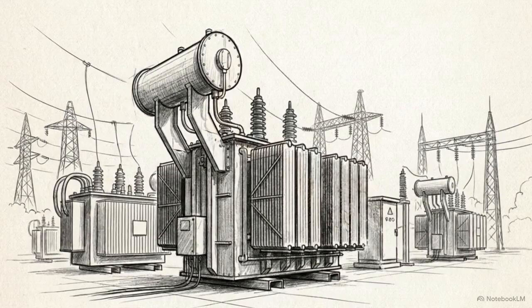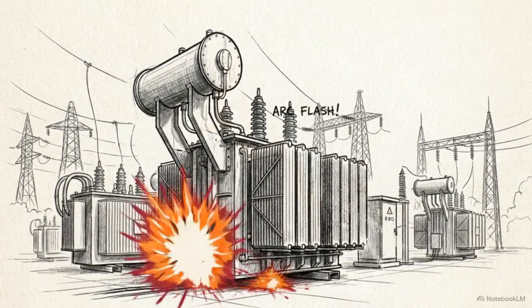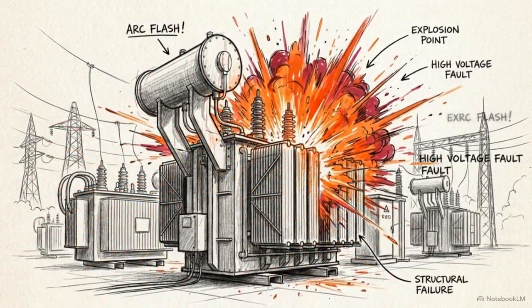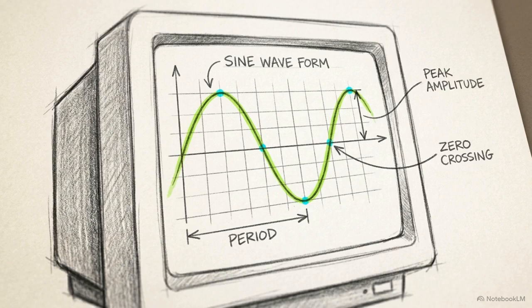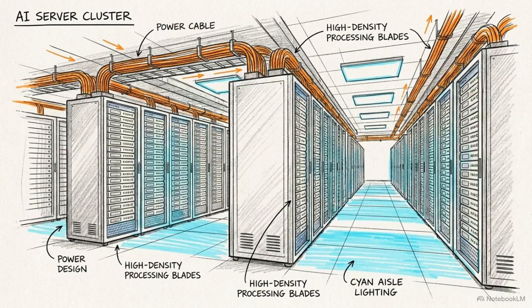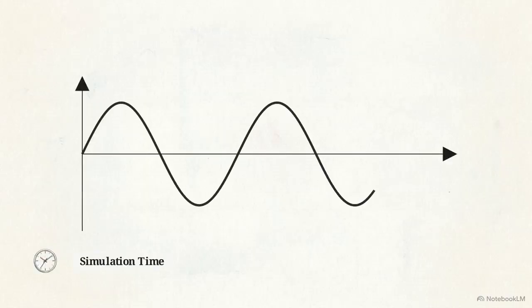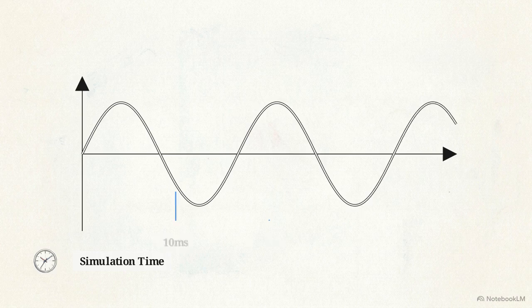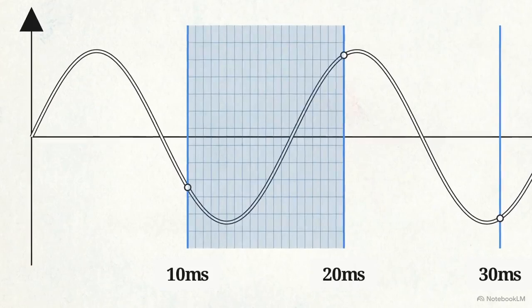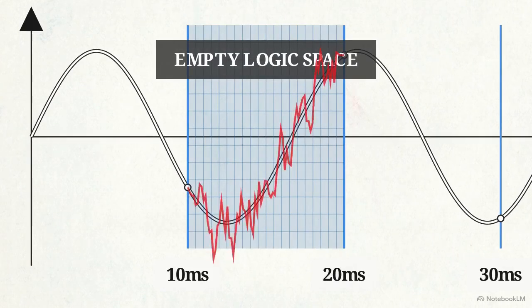When a massive power substation violently trips offline, the event happens so quickly that standard grid monitoring barely registers the cause. For decades, grid planners have relied on positive sequence phasor domain models, often called RMS, but hyperscale AI data centers possess electrical characteristics that these traditional planning tools were never designed to capture. RMS models assume a quasi-steady-state sinusoidal balance. They evaluate the grid in 10-millisecond increments, which averages away the high-speed sub-cycle dynamics where modern power electronics operate.